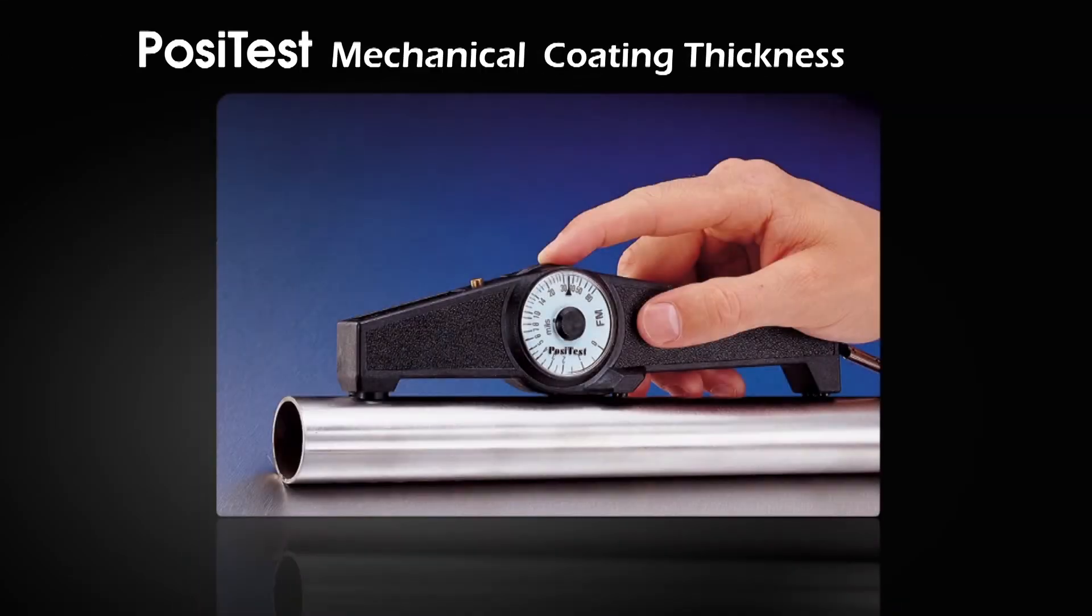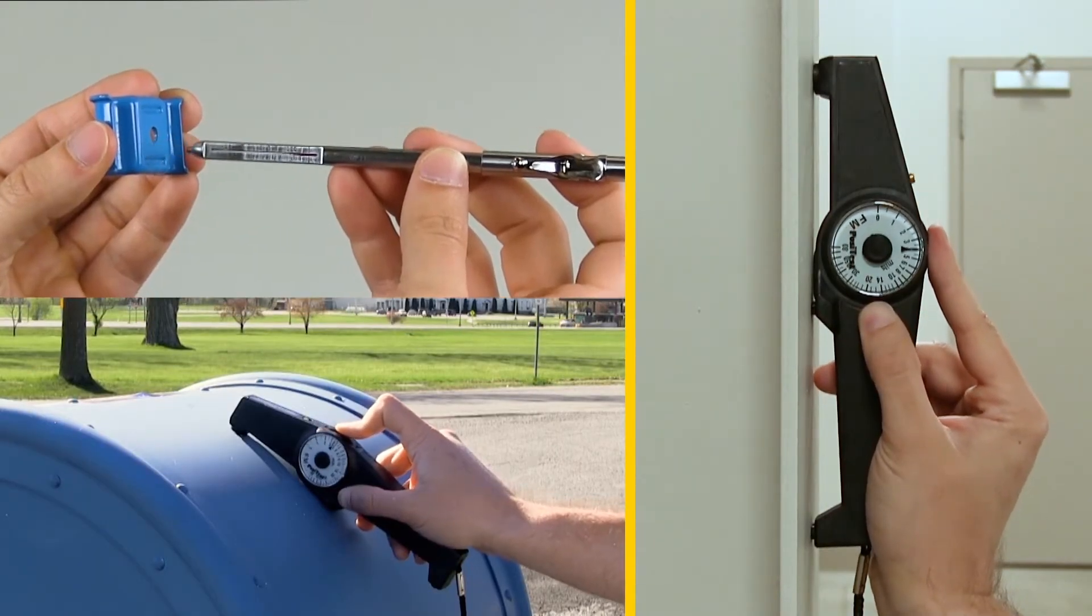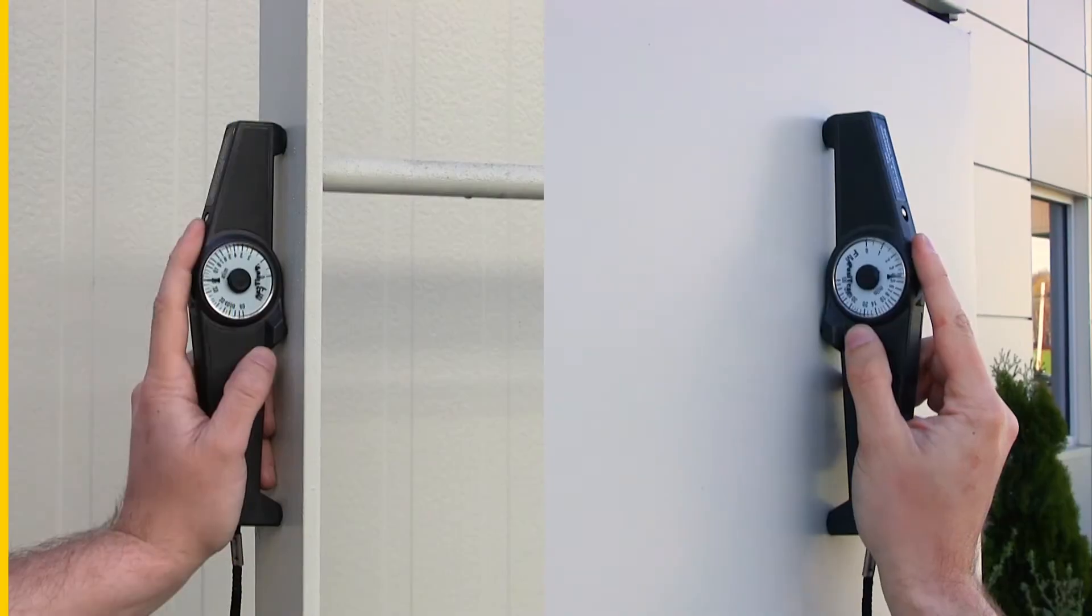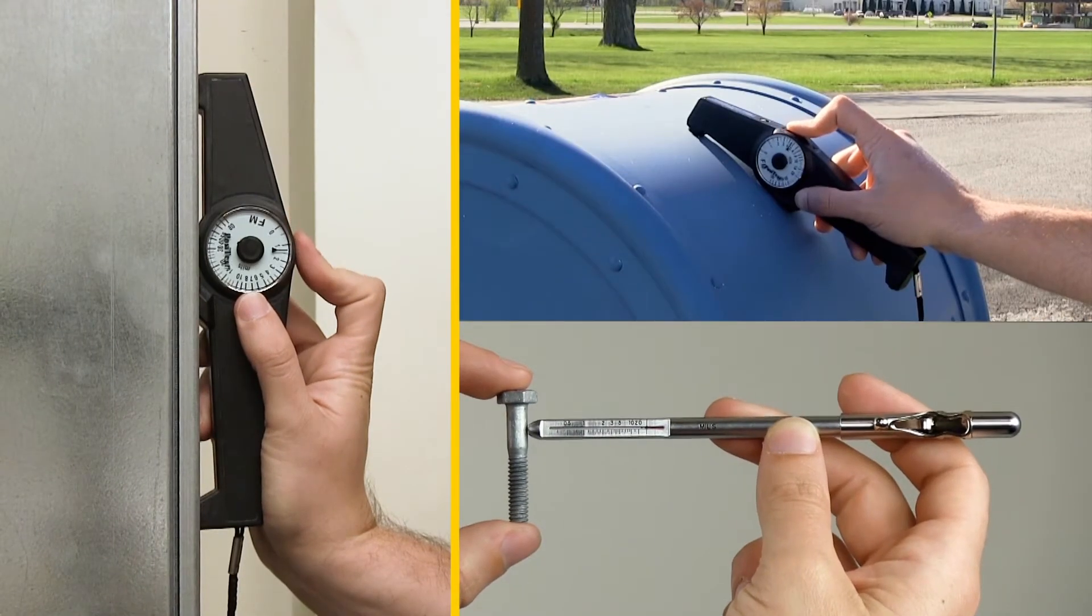The PosiPen and Positest are mechanical pull-off type 1 instruments that measure over steel substrates. They are simple to use and require no electronics or batteries. They are a rugged, low-cost alternative in situations where quality goals require only a few readings.